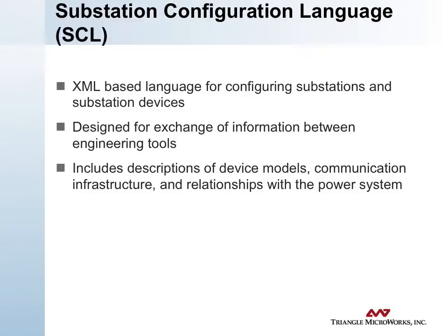I want to talk a little bit about the substation configuration language. This is an XML-based language for configuring substations and substation devices. It's designed for the exchange of information between engineering tools. It includes descriptions of the application components, device models, logical nodes, communication infrastructure, and the relationship of all of that with the power system. And this is a major innovation within 61850 that we think is going to have a really major economic impact in the overall substation automation world.